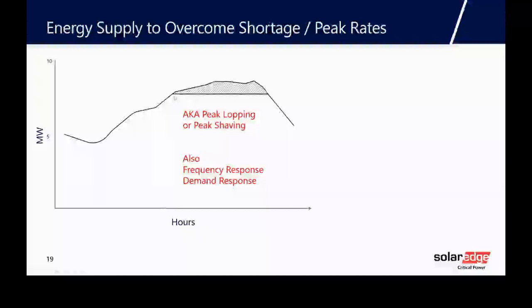They may have a limit on their power, their maximum consumption. If they go over it, they get charged a lot of money. So in those periods, we could switch our UPS to battery, or switch on our inverters from our solar energy storage to avoid them going over that limit. That's called peak lopping—it avoids you going over a limit. Peak shaving is another word for it; you can take out those peaks.